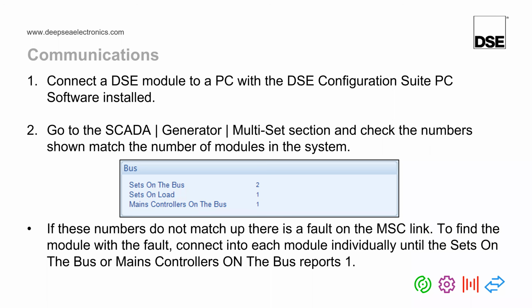Simply, if the numbers don't match up, there's a fault on the MSC link. That fault could be anything to do with cabling, incorrect termination, etc. But the easiest way to find out which controller has the fault is to go into each controller individually and look for whichever one is reporting 1 on the numbers. Because if it's only seeing itself, that means the MSC link is not working.